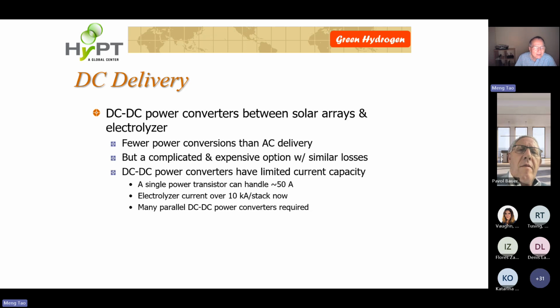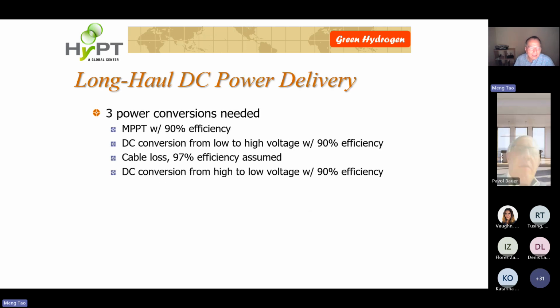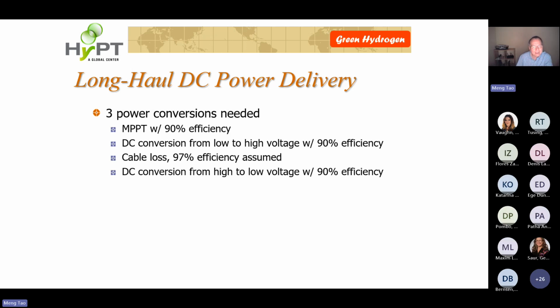But even say we can develop a power transistor which can handle 10 kiloamps, let's see whether it's more efficient. That's the other argument I have. I don't believe we need to even bother with DC power converters. Now, for long haul DC power delivery, we need 3 power conversions. We need maximum power point tracking, then DC conversion from low voltage to high voltage, which is 90% efficient, maximum power point tracking, 90% efficient, cable loss, 97% efficient, and once the power reaches the electrolyzer, we need another DC conversion to get to low voltage, so that's 90%. So you can see how much loss is there.